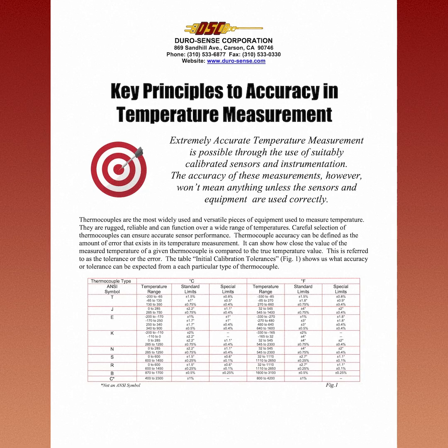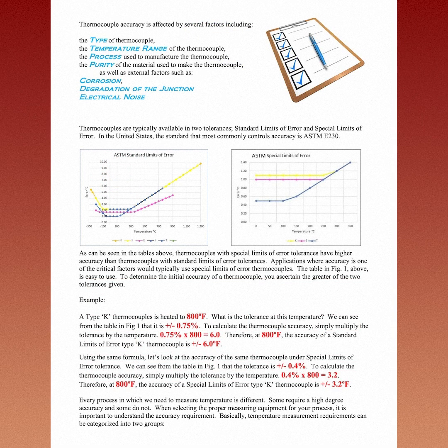Thermocouple accuracy can be defined as the amount of error that exists in its temperature measurement. It can show how close the value of the measured temperature of a given thermocouple is compared to the true temperature value. This is referred to as the tolerance or the error. The table Initial Calibration Tolerances, Fig. 1, shows us what accuracy or tolerance can be expected from each particular type of thermocouple. Thermocouple accuracy is affected by several factors including the type of thermocouple, the temperature range of the thermocouple, the process used to manufacture the thermocouple, the purity of the material used to make the thermocouple, as well as external factors such as corrosion, degradation of the junction, electrical noise.